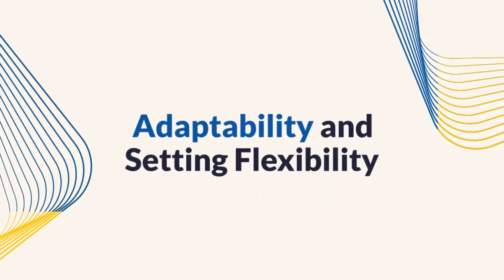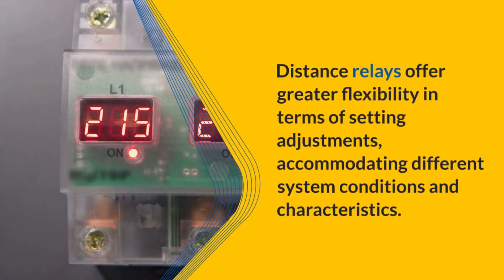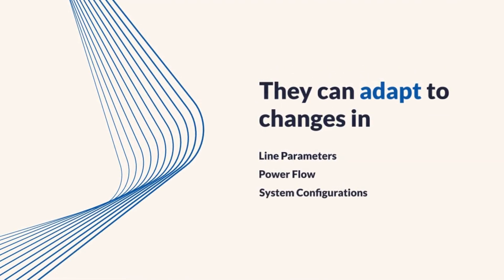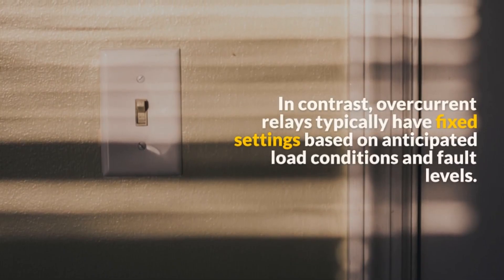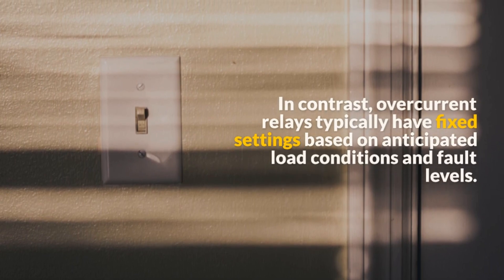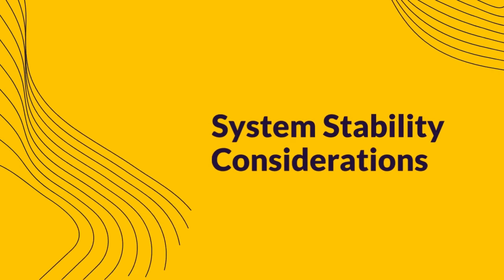Four: adaptability and setting flexibility. Distance relays offer greater flexibility in terms of setting adjustments and can accommodate different system conditions and characteristics. They can be set to adapt to changes in line parameters, power flow, and system configurations. Overcurrent relays, on the other hand, typically have fixed settings based on anticipated load conditions and fault levels.